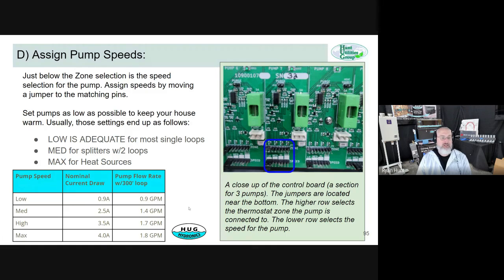And the max speed, you see there's almost no difference between high and max, but it takes a lot of extra power. Definitely recommend for floor loops, you keep it low and medium. Max is only for the heat source pump, where you want to get all the flow through it you can.